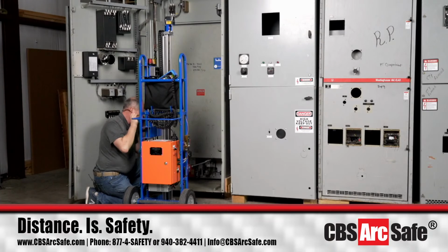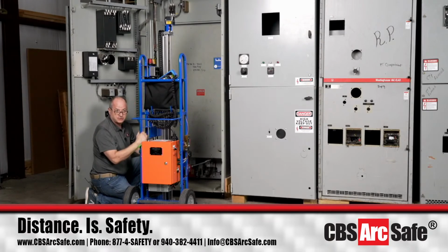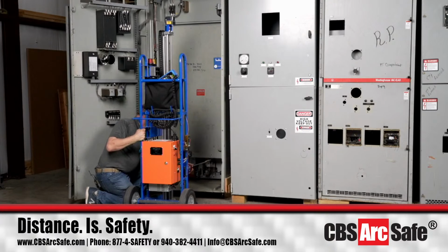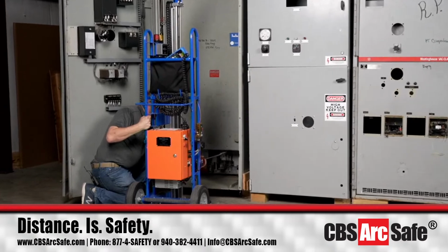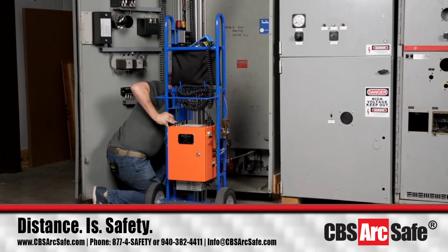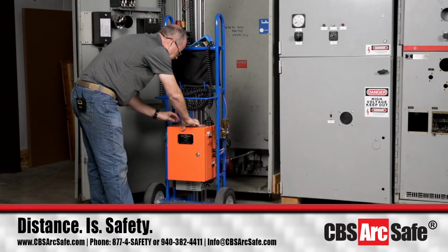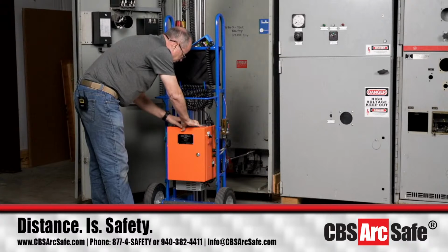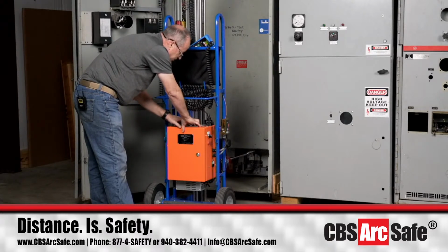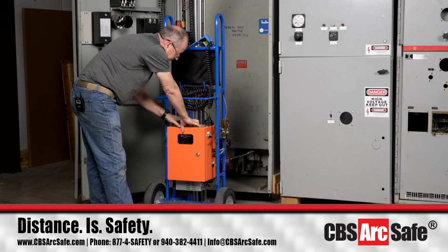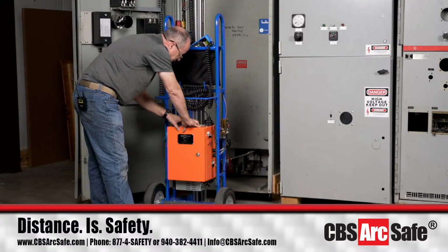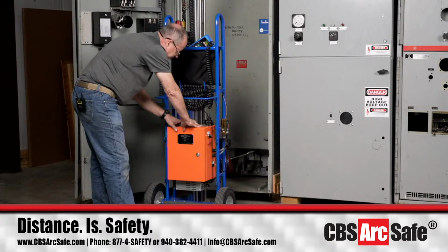Brakes off. Let me just turn my glasses on. Normally I would do this from the other side of the machine, but so that you can watch, I'm doing it from the back side of the machine right now. Okay. We will still set a force limit on the breaker in terms of how much force we're going to let it generate. Playing with these breakers in various facilities, I'm going to set the install value at 19 and the remove at 15. And that's a fairly good number for this type of circuit breaker.